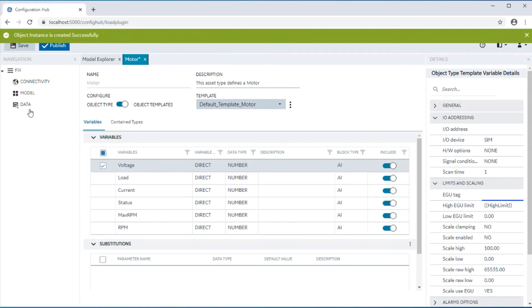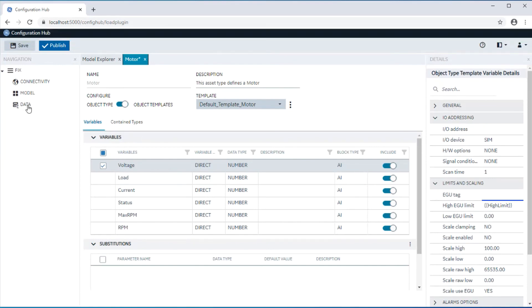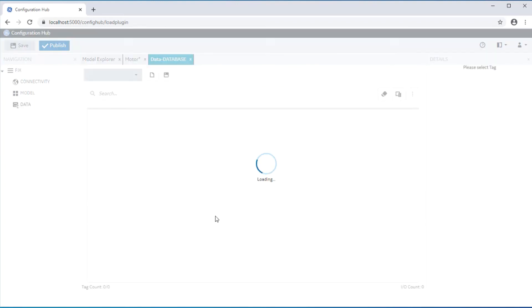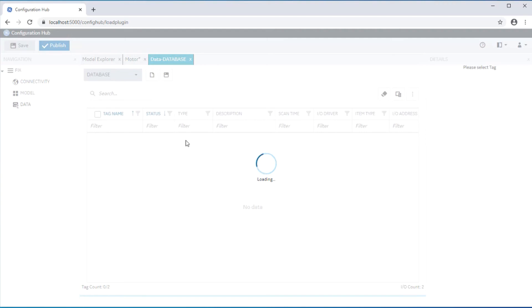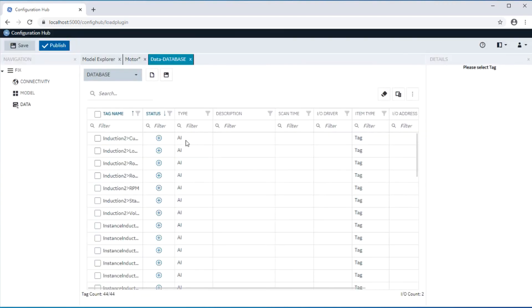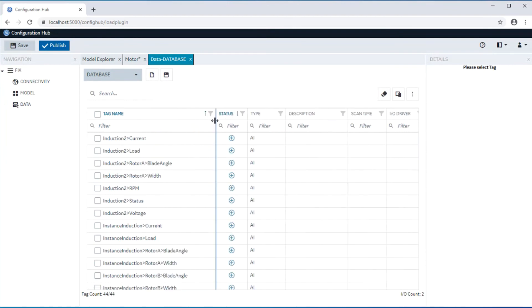The variables will be created as tags in the IFIX tag database. Moving into the database panel in Configuration Hub, you will notice that the new instances have a complete path to the new instance along with the variable name created as an IFIX tag. You will also notice that the block type is picked up from the way it is defined in the template.